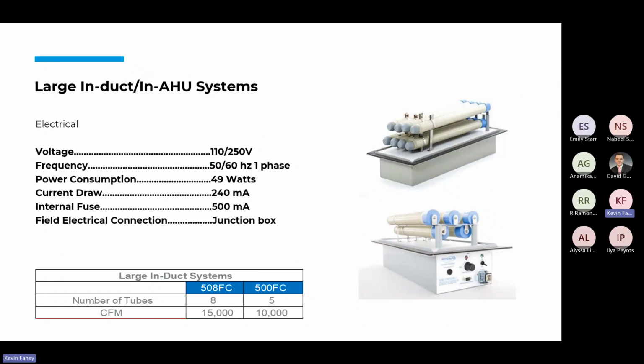So you could literally power this off the light switch, or the lighting in an air handler, or in the room near the mechanical room. It draws not only a quarter of an amp, but the power consumption is 49 watts, so it doesn't use more power than an incandescent light bulb. And the third thing that's nice is there's relatively no pressure drop. Something like this is just under 2/10 of an inch pressure drop, because you're not filling the entire duct, not like a filter where all the air has to pass through it. Just a portion of the air passes over these tubes.